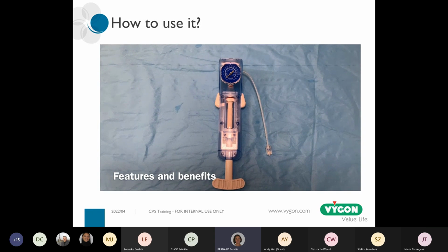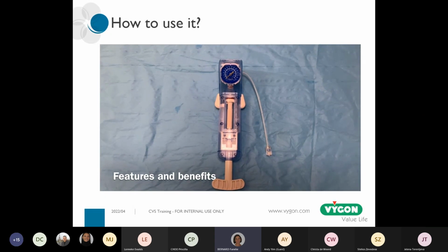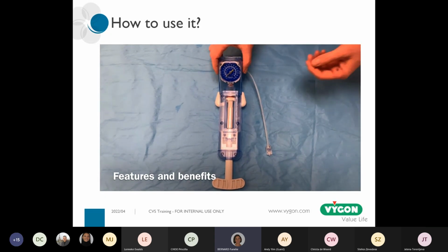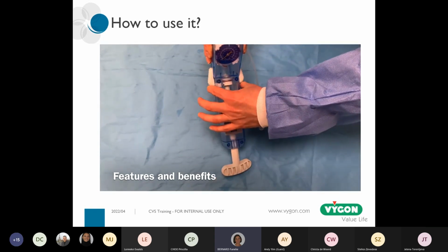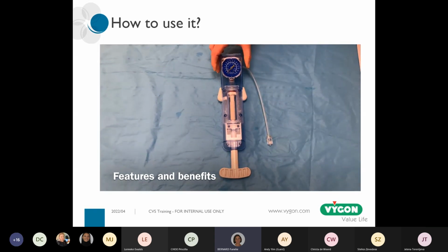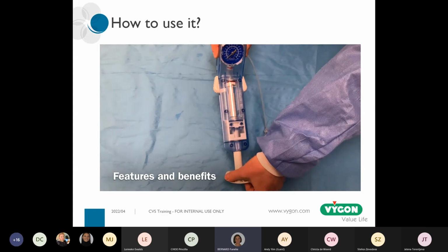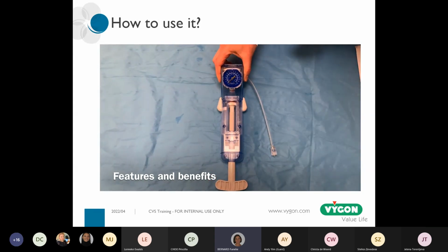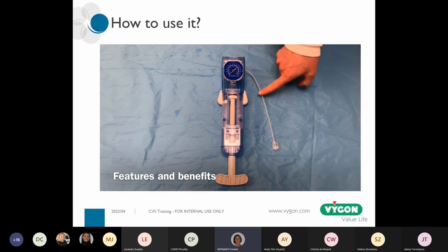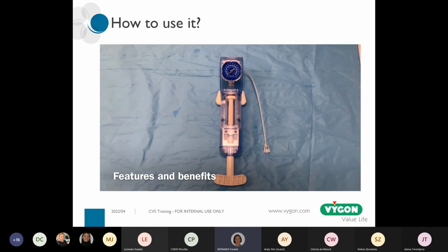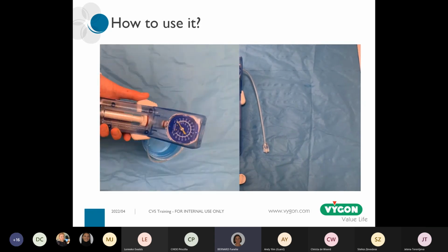The syringe is transparent to see and remove bubbles easily. The maximal volume is 30 cc, so the Dolphin is suitable for small to big balloons. The locking system is automatic. It has a T-shaped handle. The Dolphin has a square shape to be stable on the table. It has a PU connection line with or without a three-way stopcock.